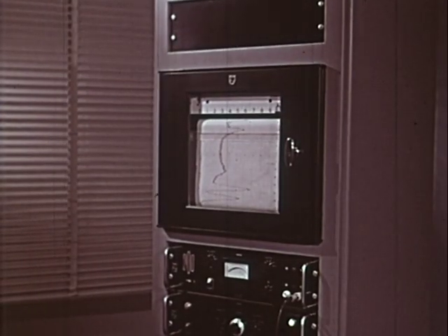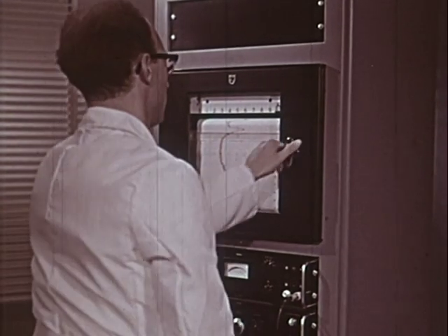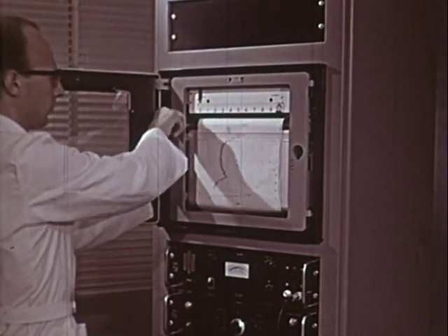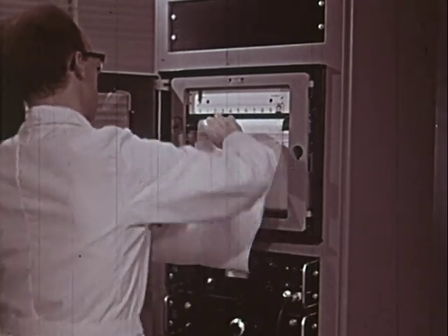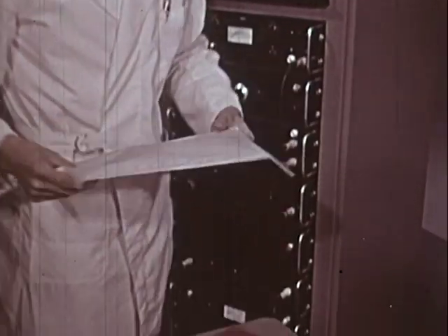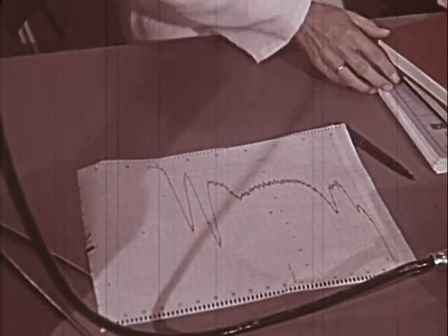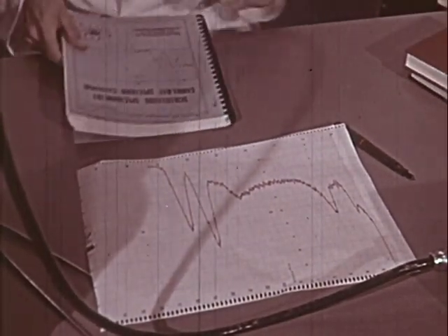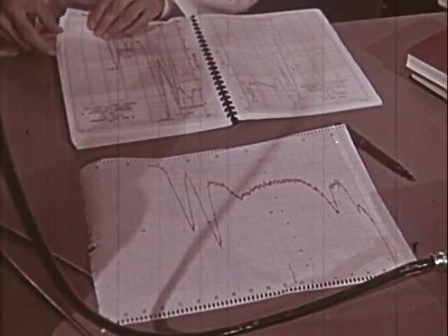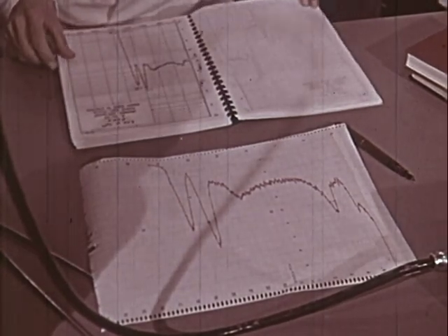When the graph presenting the record of the gamma energy spectrum is completed, the equipment automatically stops scanning. The energy levels of the peaks in the spectrum directly indicate which nuclides are present in the sample under investigation. Existing handbooks contain all data on energy distribution of gamma-emitting nuclides. By determining the area of a peak, a direct measure for the quantity of a certain isotope in the sample is obtained.